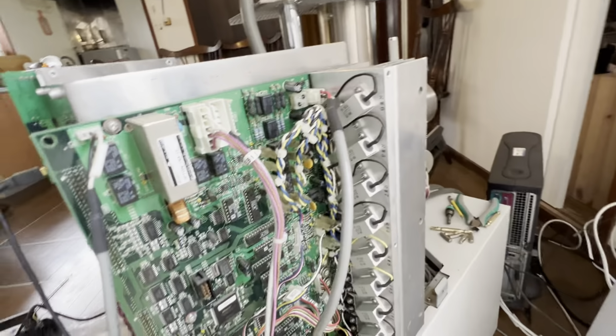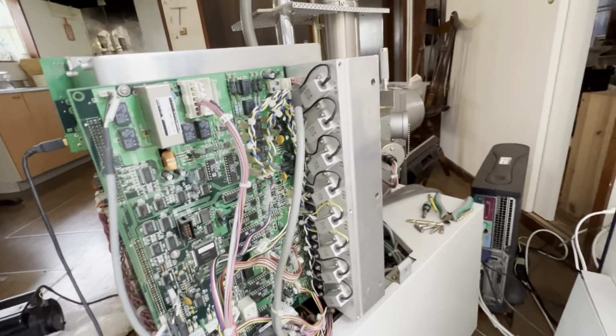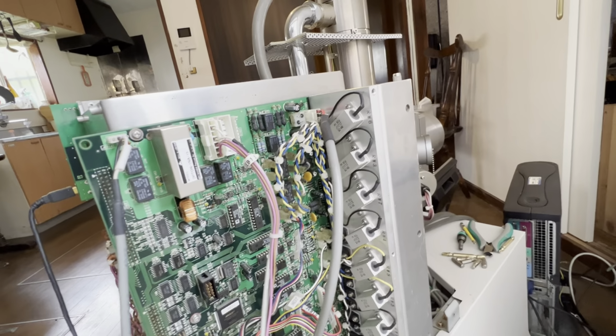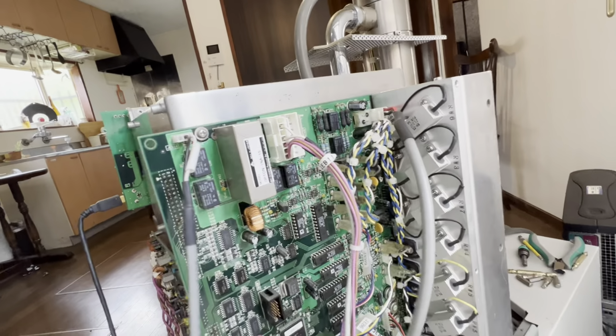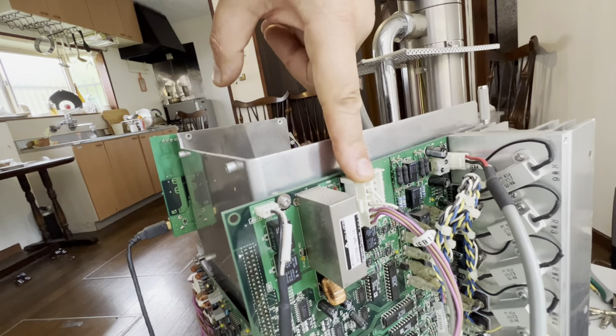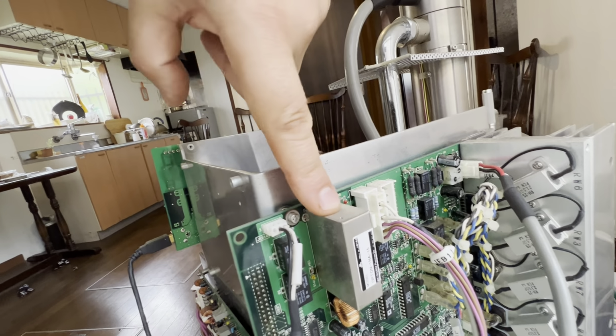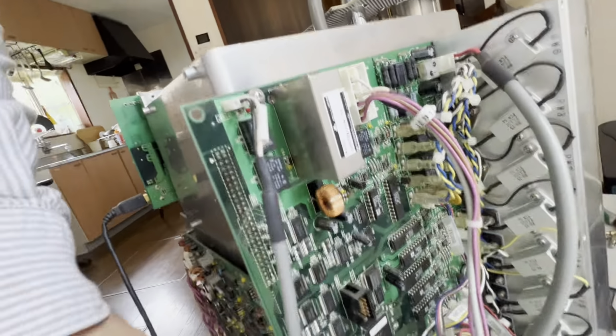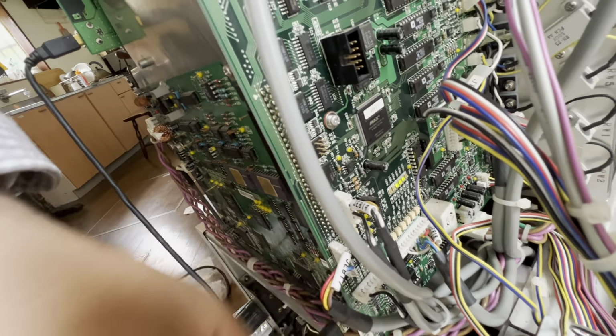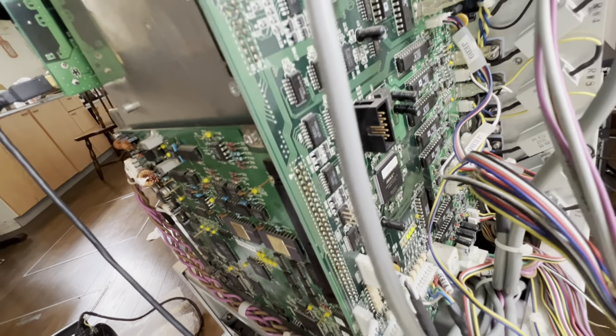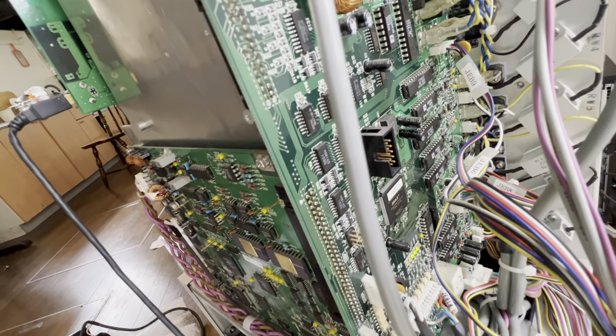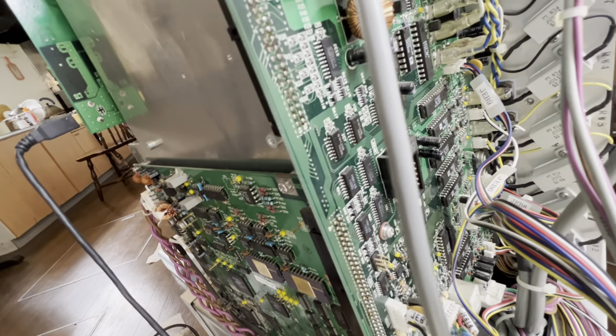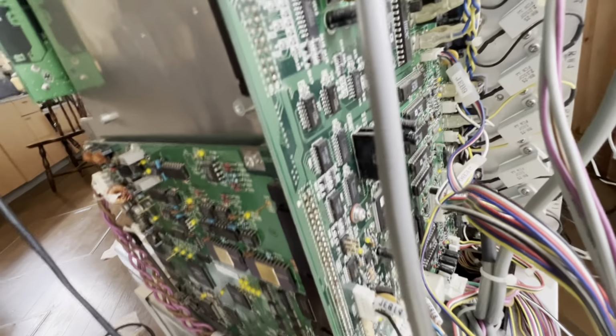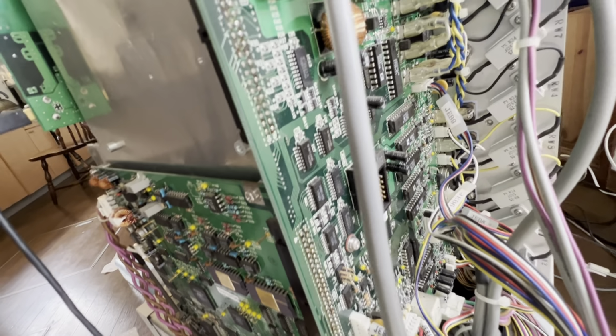On the other side, there's this board with an FPGA on it, plus a stack of DACs. This is where the PMT connects, and this is a PMT power module. The turbo connects here, and I have some notes on that showing the connection. The analog output of the turbo, the motor speed, is not connected - it only reads set point and error conditions.